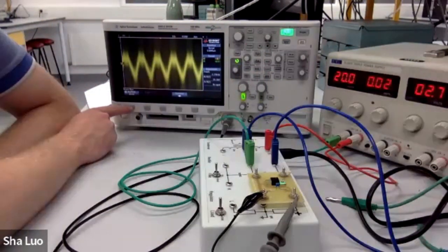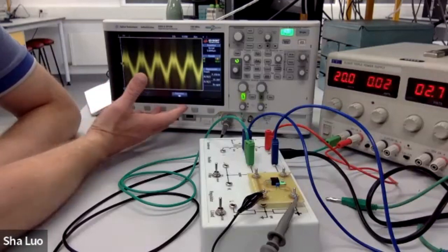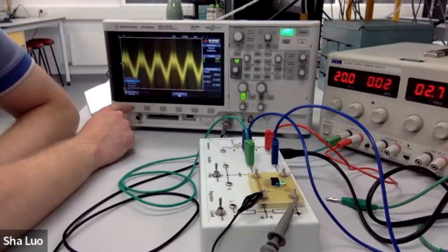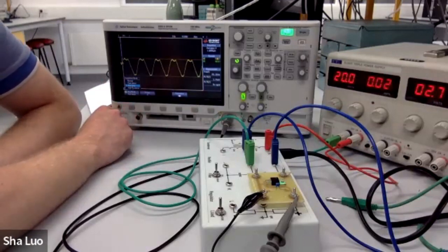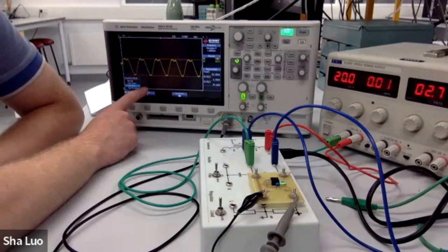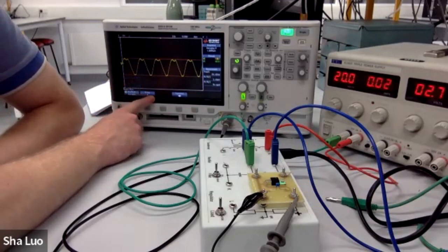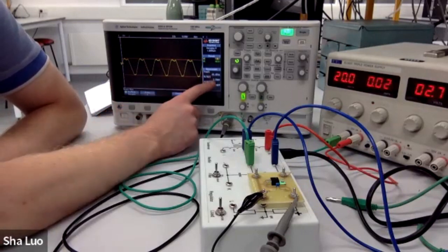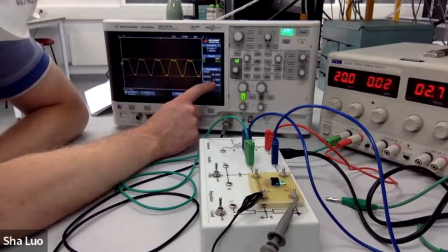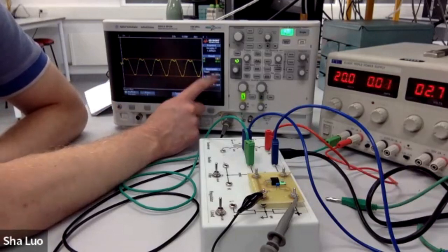Currently, we are set to normal acquisition mode, which is basically just sample what's there. I can change that to an averaging mode. There's also this high resolution mode, which does a similar but slightly different thing. If I put on the averaging mode, with 8 samples for averaging, I can now more accurately measure the peak to peak ripple. Our output peak to peak ripple is 2.58 millivolts. So 2.58 millivolts of output ripple.